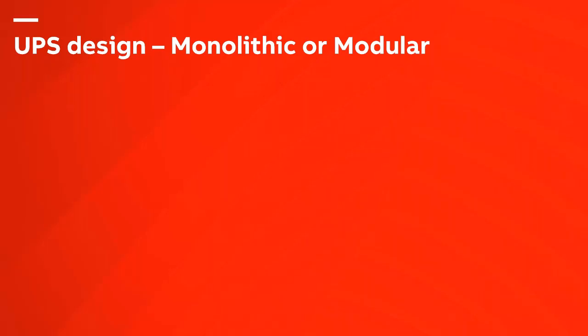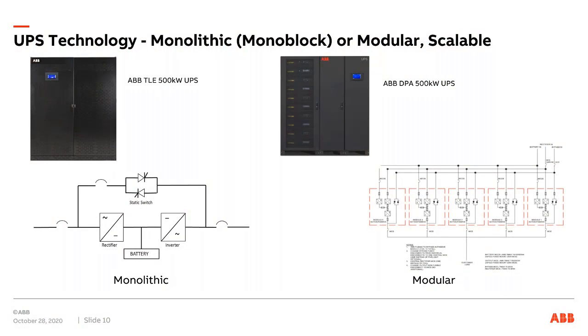And then, getting a little closer to what will be the rest of the presentation, we have modular UPSs. The UPSs I've been talking about so far are what we refer to as monolithic. Like a 500 kW is a 500 kW. That's what it knows. That's what it's designed for. Everything in the UPS is rated to support 500 kW, so the rectifier, the inverter, and the static switch are designed for that. If you need more power, like we just talked about, we have to parallel another 500, or it could be a 750 or 1 megawatt, but 500 just as an example. And we can parallel more of them, and we can support more power.